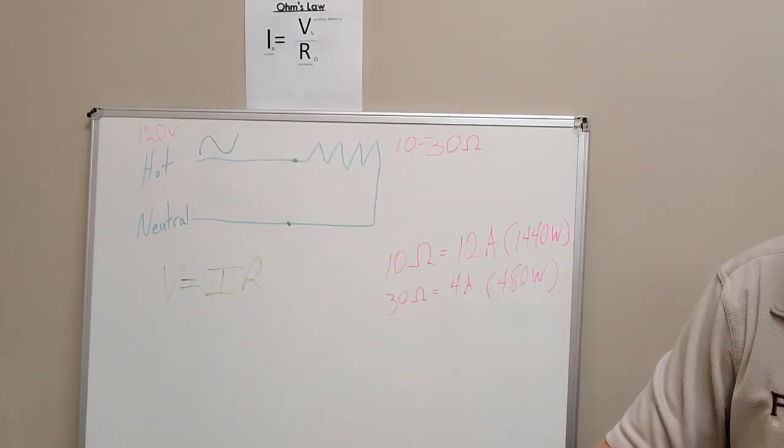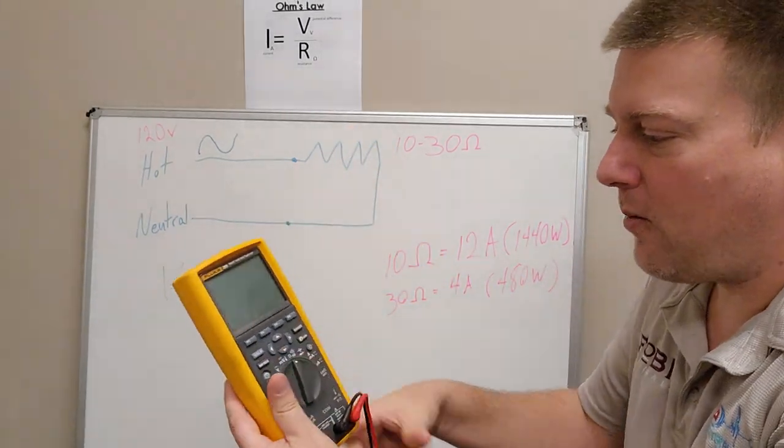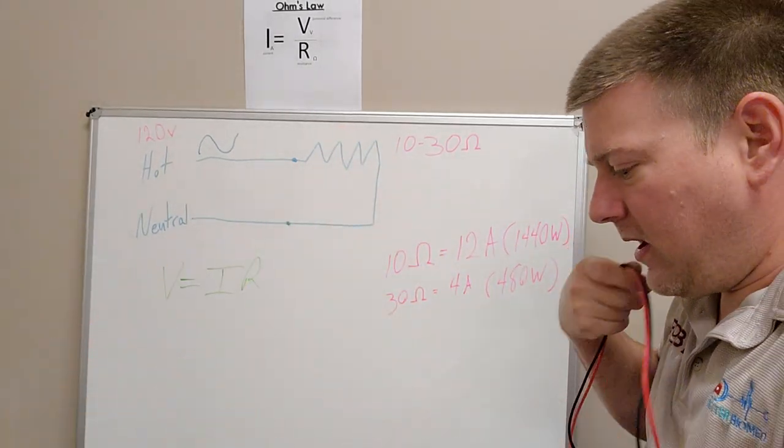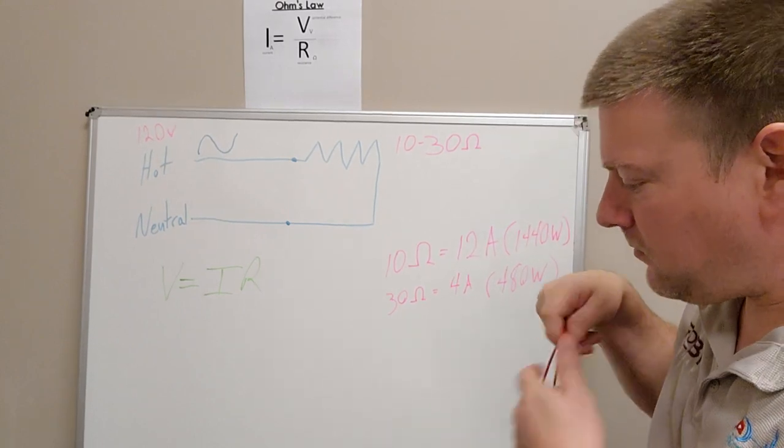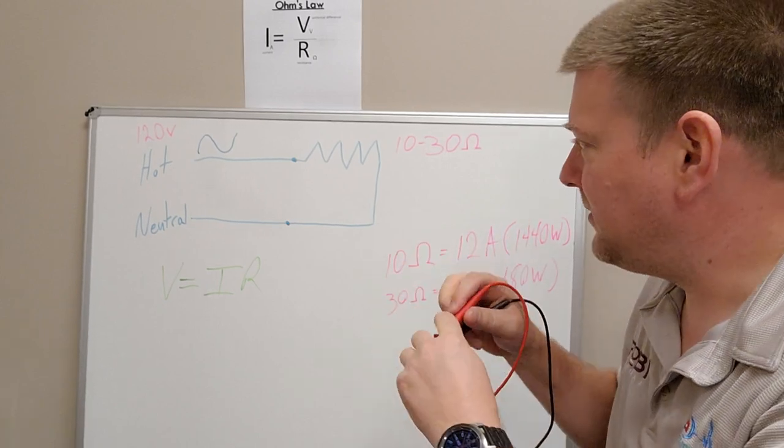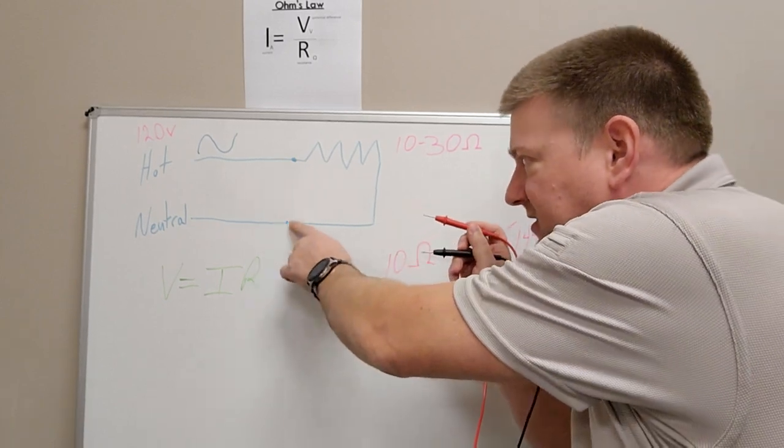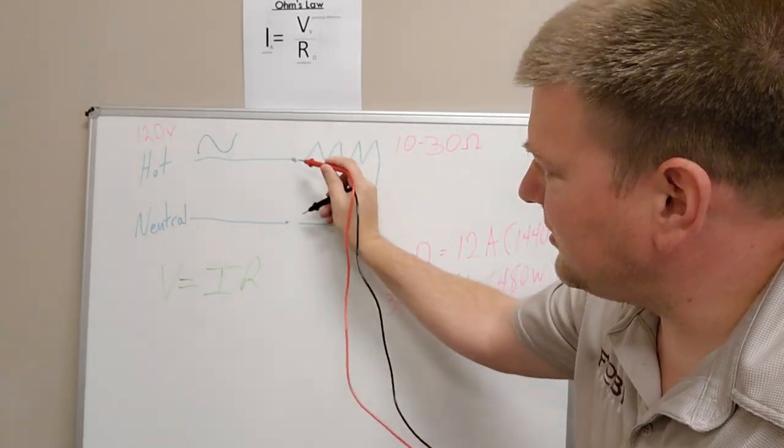As I said, when you're testing, you're going to have your multimeter on ohms. Let's set this guy up proper. When your meter is on ohms, with one hand you are going to disconnect one lead, and when one lead is disconnected you will run it. Of course, the device isn't plugged in.